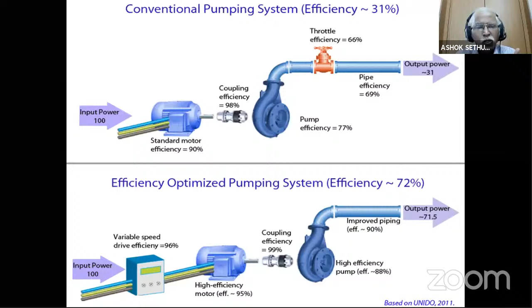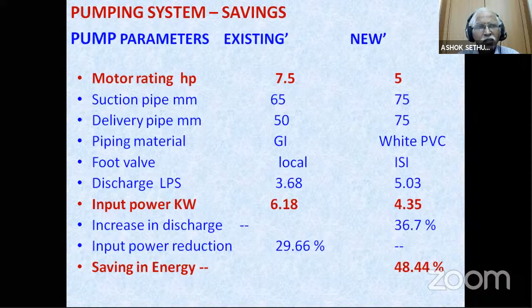You can try it in your college, in all your water pumps, and study the results, and then you just publish it. This is what we want. Showcase the energy conservation case studies from your college and then publish them in papers. This is what the industry wants from you. See, the piping sizes also have been changed from 2.5 inch to 1 inch, 2 inch. They have made it 3 inch pipes. And all the foot valves, they have made 15% larger in size to increase the suction, to maintain the NPSH, net positive suction head, excellently.